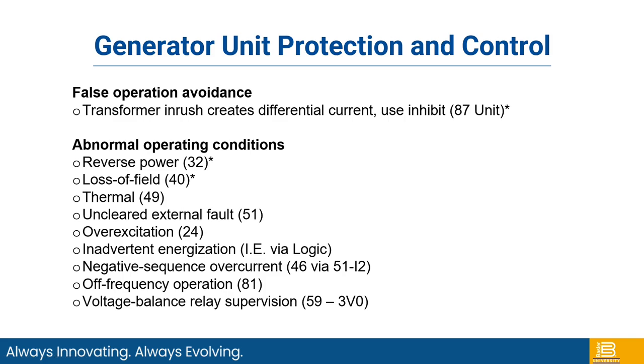This is typical protection that would be used. Note we have a generator application guide and a transformer application guide if you need more information on consideration for those types of protection. So reverse power, loss of field, your thermal protection with the 49TC or the 49RTD, both are available. Uncleared external fault with the 51, overexcitation, and inadvertent energization, which is done via logic.